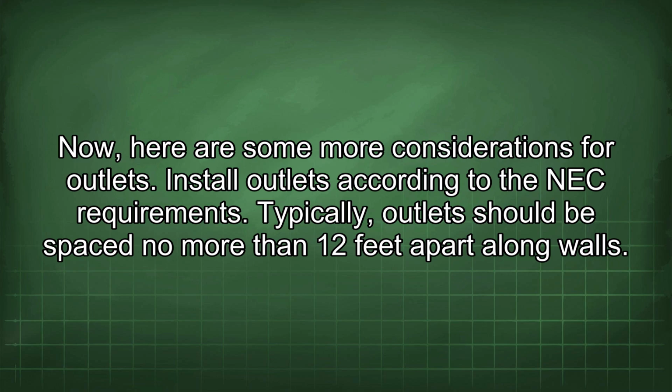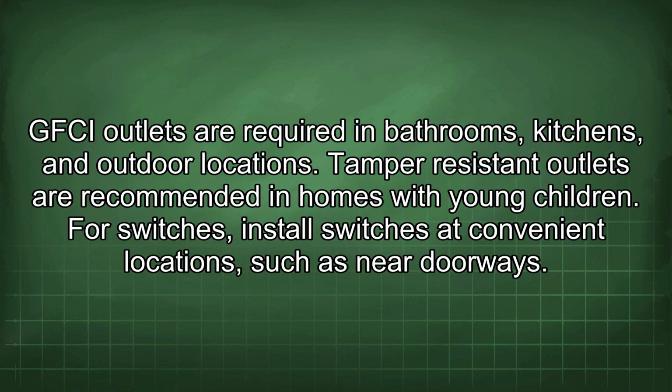Install outlets according to the NEC requirements. Typically, outlets should be spaced no more than 12 feet apart along walls. GFCI outlets are required in bathrooms, kitchens, and outdoor locations. Tamper-resistant outlets are recommended in homes with young children.